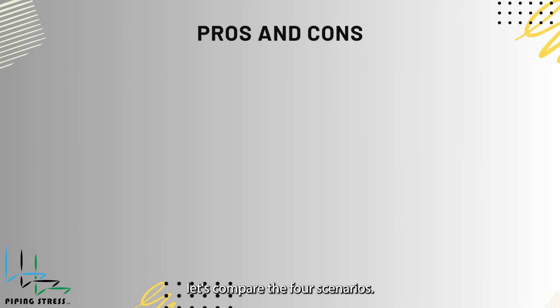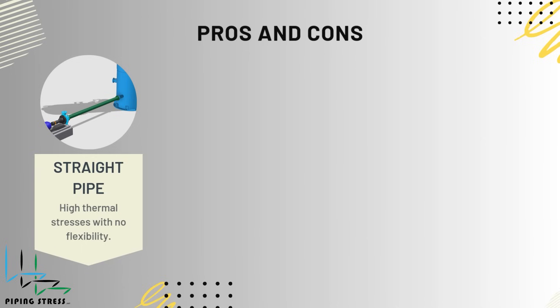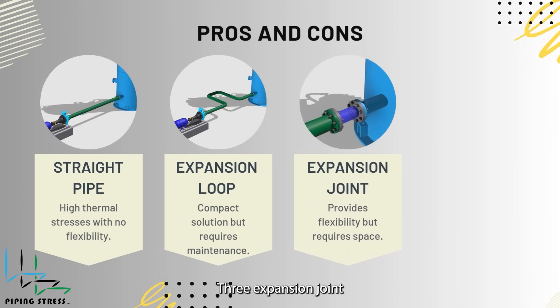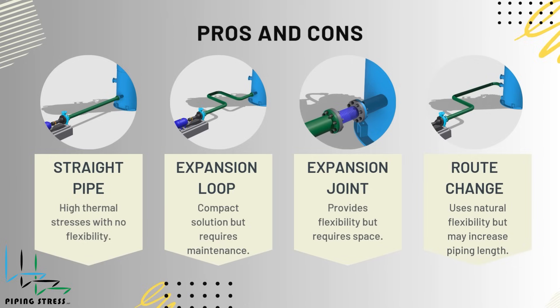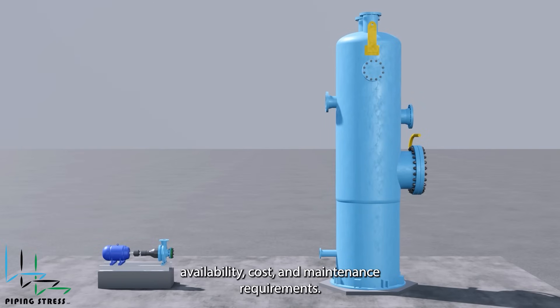To summarize, let's compare the four scenarios. One: straight pipe — high thermal stresses with no flexibility. Two: expansion loop — provides flexibility but requires space. Three: expansion joint — compact solution but requires maintenance. Four: pipe route change — uses natural flexibility but may increase piping length. Each solution has its pros and cons, and the choice depends on factors like space availability, cost, and maintenance requirements.